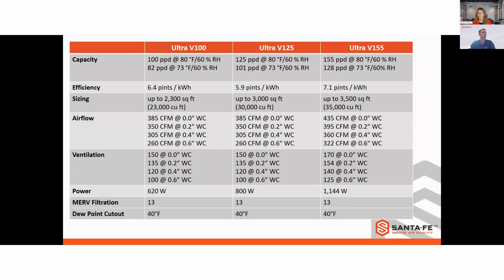And then airflow is also where these units really shine. We were able to incorporate a stronger blower into these units, and that was really to be able to overcome the statics that we are seeing on a lot of our higher performance HVAC systems. Also, retrofit, we're very commonly used and called to fix problems. And that existing ductwork might not be able to traditionally handle a whole house ventilating dehumidifier, but now we've got this fan. Now, we should always be fixing ductwork when possible, but understanding that we do have some more blower capacity on these.